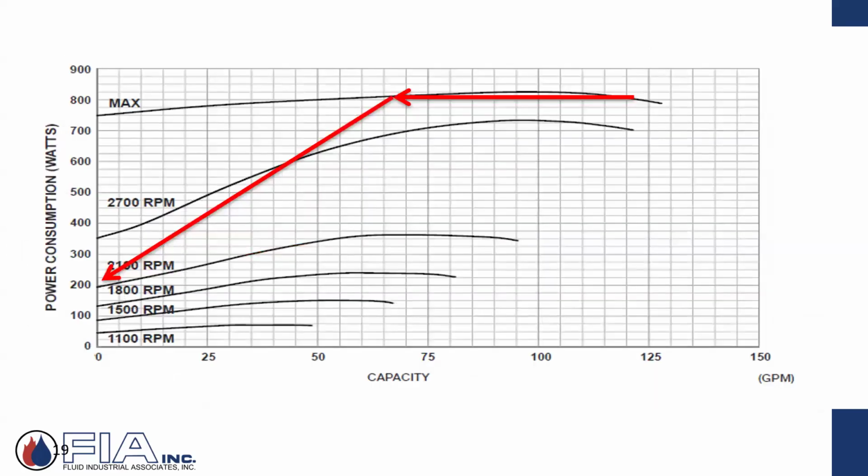When we start looking at the power consumption on that exact same curve, you're going from whatever, 800, give or take, watts, and depending upon performance, what's happening in the zones, and they're closing and this thing's backing down, you could be down around 300, 250, 200, 220, whatever. So that's the beauty, and that's why the drive or the interest.